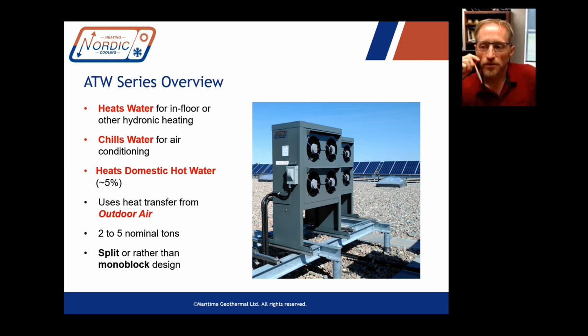I guess if you're talking about lower capacities, like small model sizes for passive houses, that would be something to take into account, because people who live in a passive house aren't necessarily using correspondingly less hot water. So that rule of thumb might not hold up if you only have a 2-ton heat pump, due to there not being a very high cooling and heating load, but you would have the same domestic water load as perhaps a regular house. So maybe it wouldn't do all the domestic water heating for a typical household in the middle of winter. But that's the traditional rule of thumb anyway.